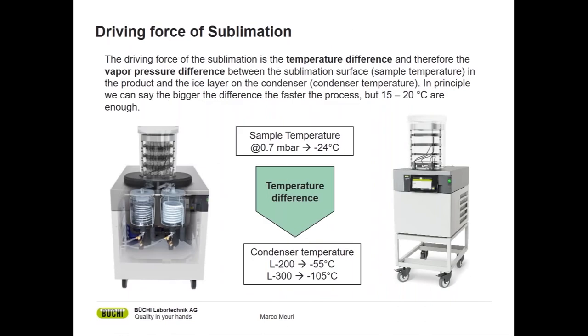The pressure is used in the range of one millibar down to 0.03 millibar, depending on the sample temperature we want to achieve. The sample temperature is important because the driving force of sublimation is the temperature difference between the condenser — in the actual freeze dryer — and the sample temperature. The sample in the freeze dryer sits on top, either in a chamber or attached as a manifold.